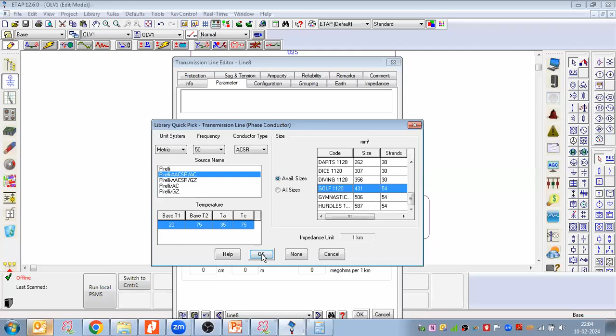After clicking OK and going to impedance, you'll see nothing yet, so let me put the configurations. Using the selected parameters, I set the transmission tower height above ground to 24 meters, since 400 kV towers are generally built to that height.